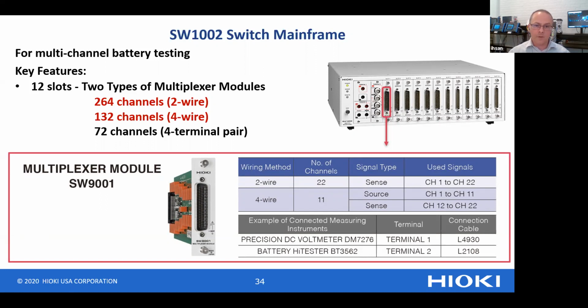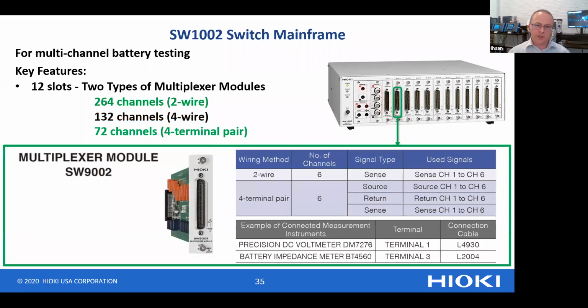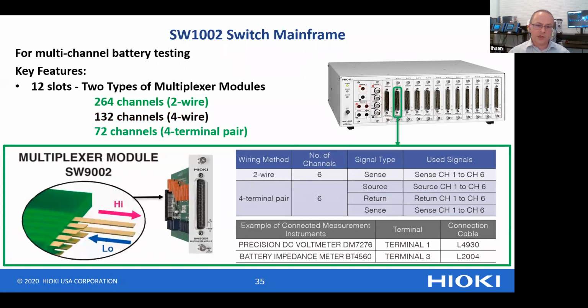And this is great for end-of-line testing, where we don't necessarily need the full frequency sweep. We also have a different multiplexer module, which is known as the 9002. The 9002 is also capable of the 4-terminal pair method, so it's more suitable for cell grading, where you have to sweep through a range of frequencies. The board is laid out in such a way that the return test currents and the test currents are arranged so that the effect of the induction error on the sense line is minimized. If you were to try and create an off-the-shelf multiplexer, for instance, this would be a major challenge.